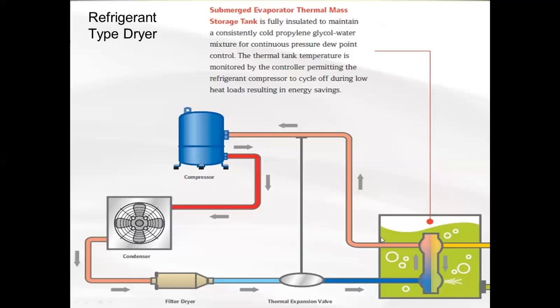Lost my pointer. There we go. If I don't keep this thing moving, it disappears on me. So this is the heat exchanger. This boils off energy from the glycol, goes into the heat exchanger on this side, boils off the refrigerant, which is the cooling effect that keeps this glycol at the right temperature. And then this is superheated vapor that travels back to the compressor. A little review of your thermodynamics on this stuff.